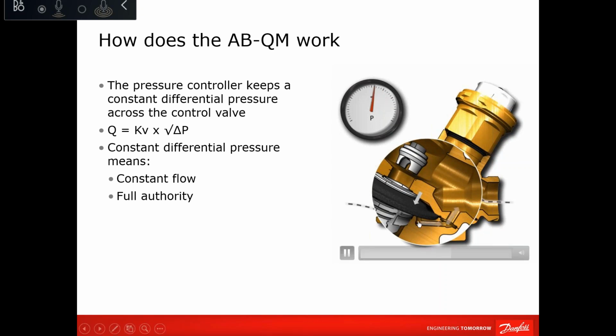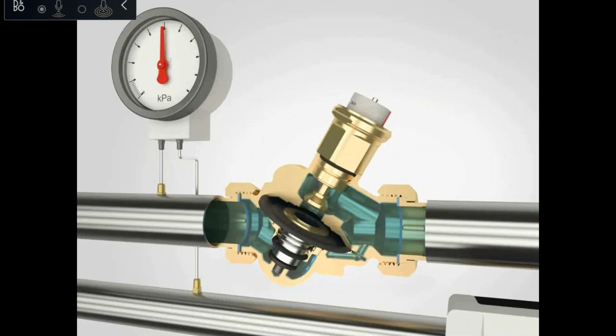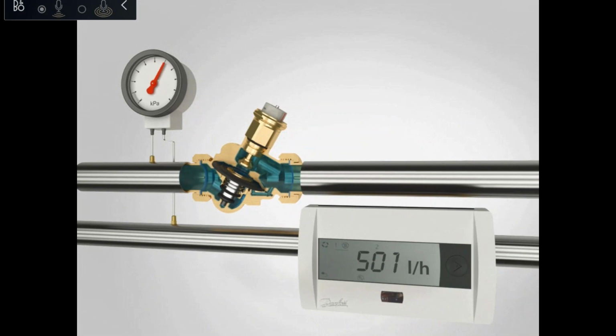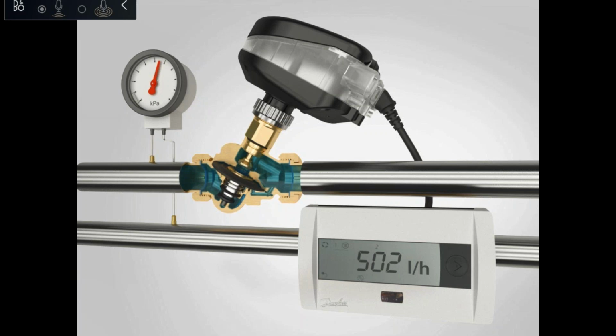So this is a zoom in inside the area. And as you can see here, the movement of the water sensing point, when it is going out, it is sucking the membrane with it, and then it is returning back to counterbalance in case the system pressure is back to normal. This is an example of water and pressure control animation. You can see very precise control due to the fact that there is no single excess of pressure from the system affecting the controllability of the PICV.